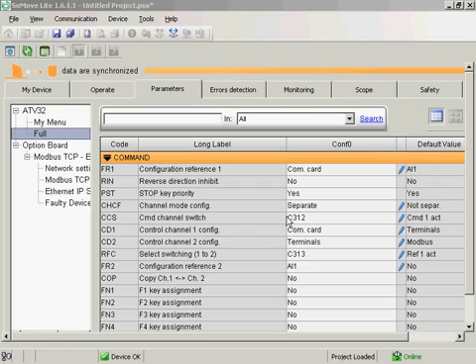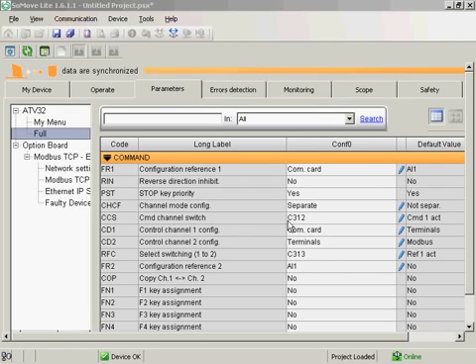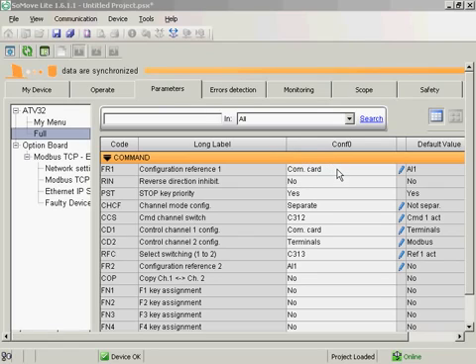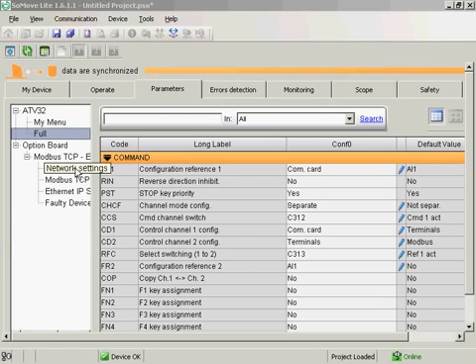I have the channel mode configuration. I've got that for separate. What this means is based on the command channel switch being bit 12, the command control is set on the com card or on the terminals based on that 12th bit. The reference switching is based on the 13th bit, and it's going to be based on the reference coming over the Modbus TCP communications or on the analog input 1.